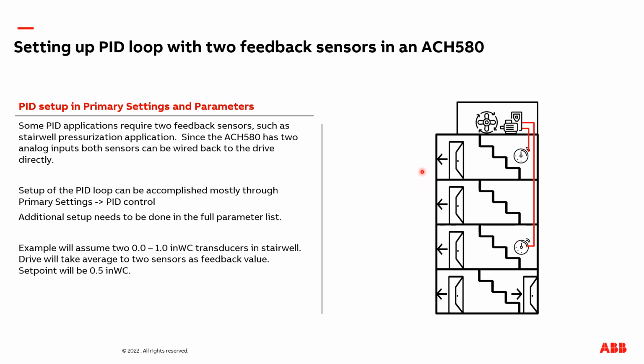In the video, I'm going to have the transducers have a range of 0 to 1 inch of water column, and I'm going to have a set point of a 1/2 inch of water column. I'm also going to set up the VFD so it takes the average of both transducers. I will also mention in the video that it is not uncommon to also maybe take the min or max of either transducer and regulate the PID loop off of that instead.